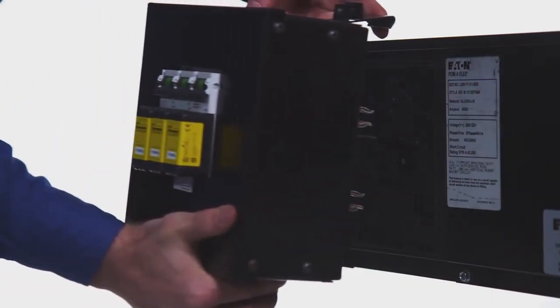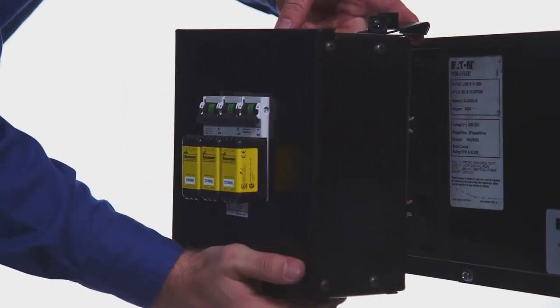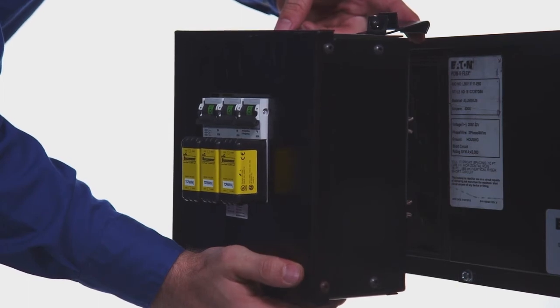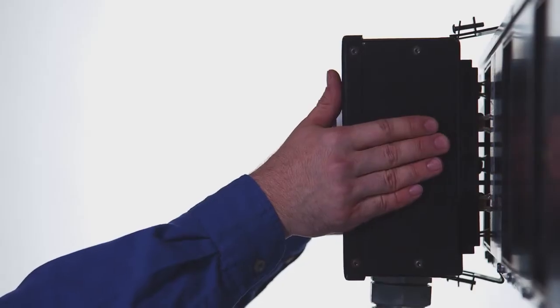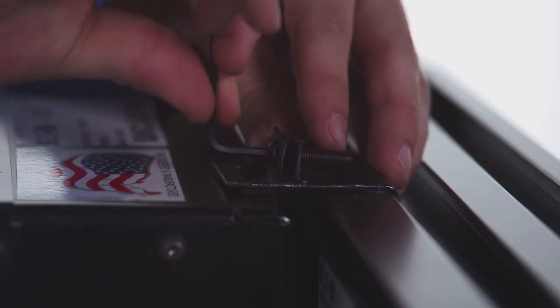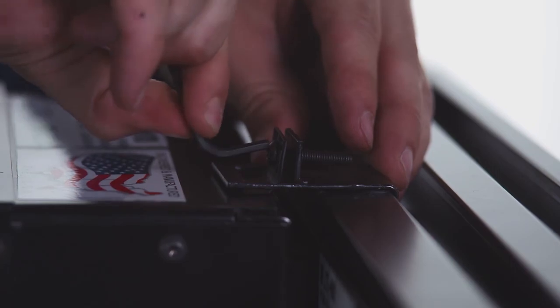Align the bus plug with the busway and guide the tabs into position over the bus housing. Push the bus plug onto the busway. A small amount of force is required to ensure that the plug stabs are fully engaged onto the bus bars. Tighten the bolts to secure the bus plug to the bus housing.